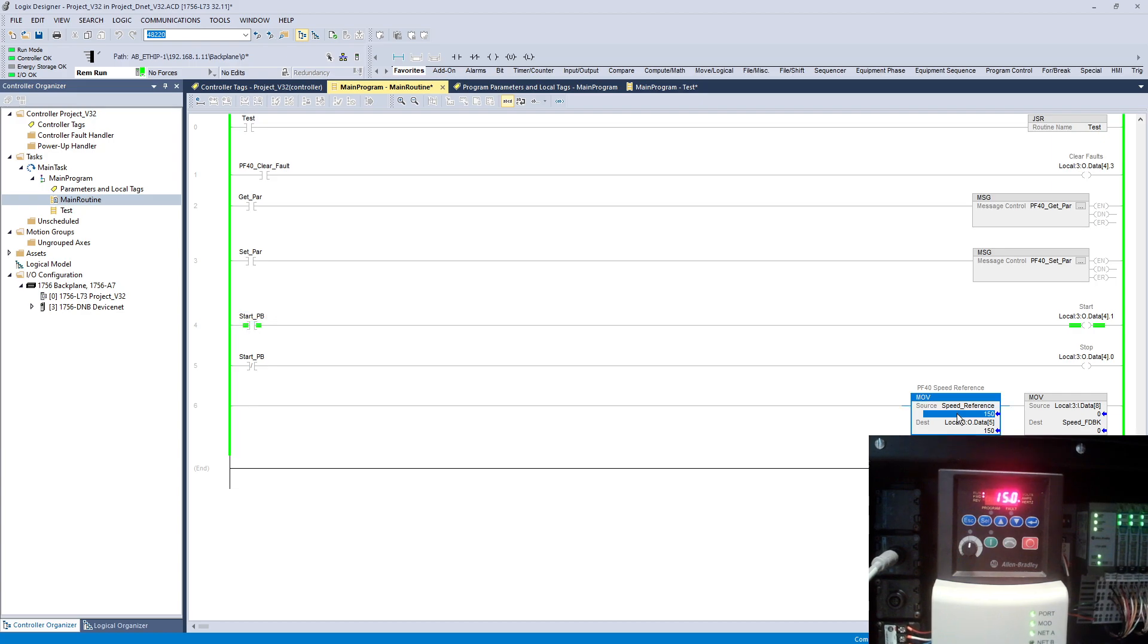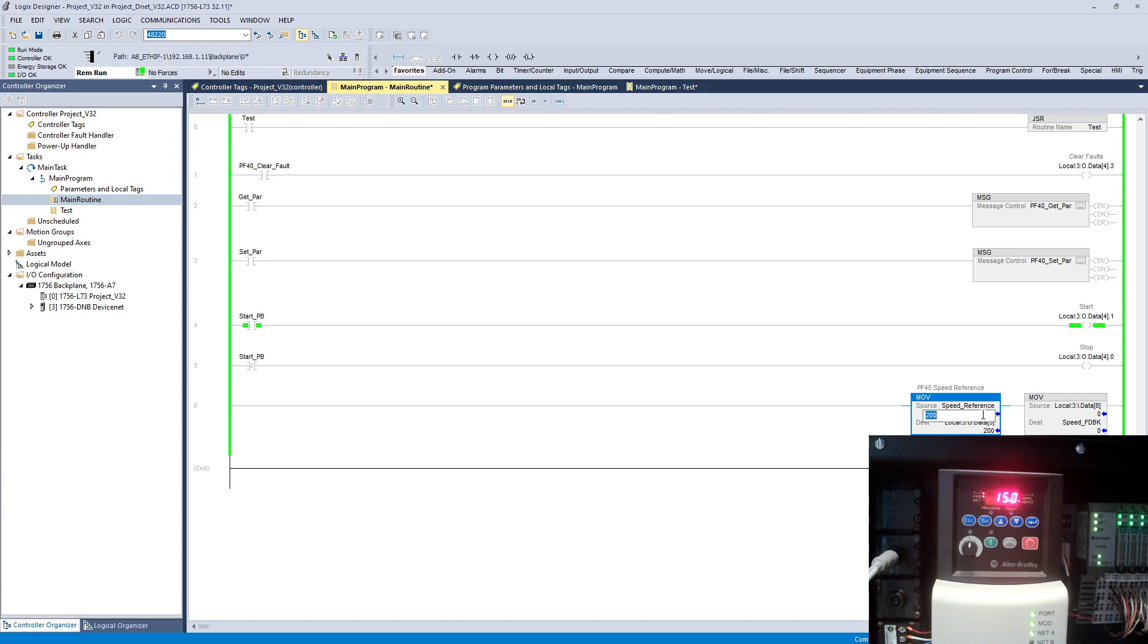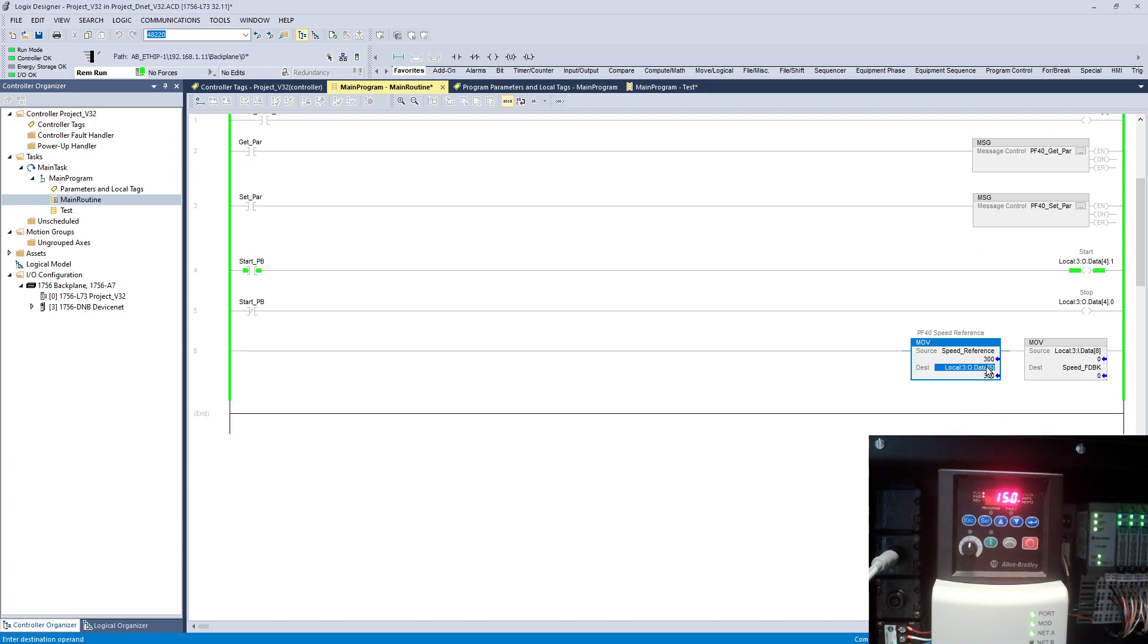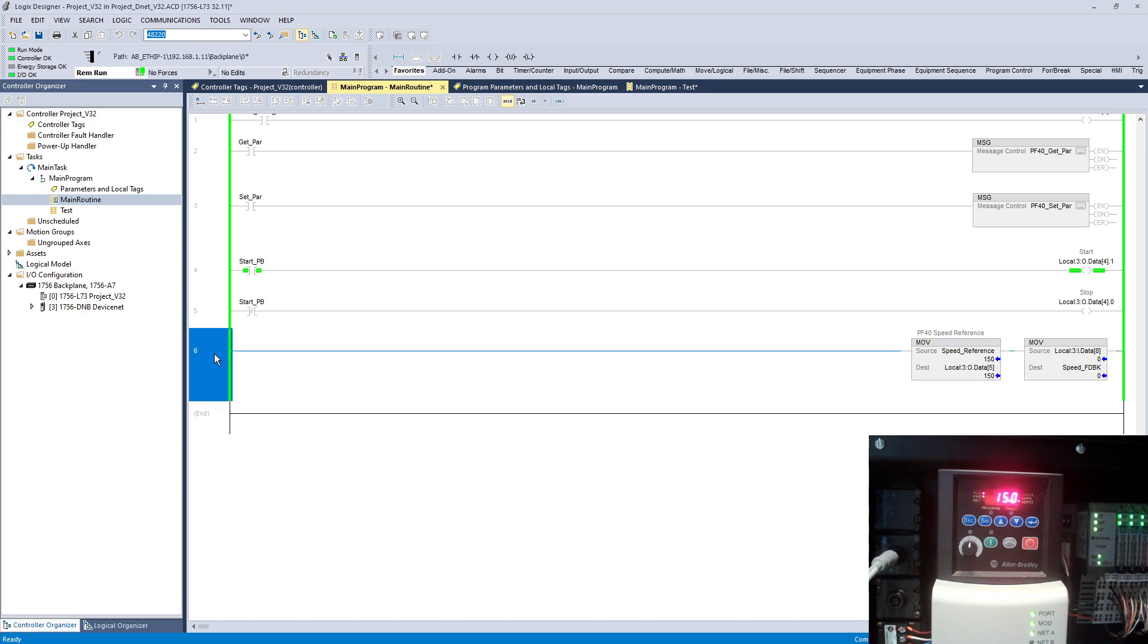Let's try that if it is taking from here. As you can see it's not taking from here anymore. If I put here 300, nothing is changing on the VFD side. The reason why is because I'm taking it from somewhere else.